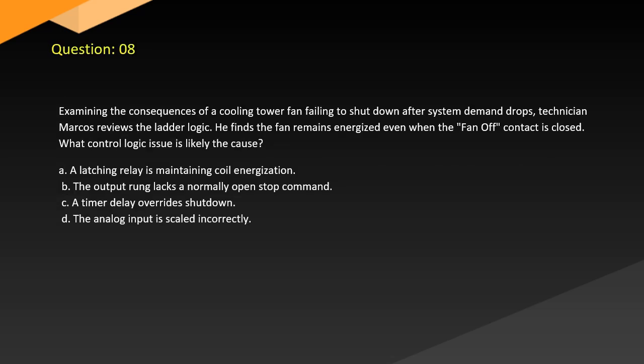Question 8. Examining the consequences of a cooling tower fan failing to shut down after system demand drops, technician Marcos reviews the ladder logic. He finds the fan remains energized even when the fan off contact is closed. What control logic issue is likely the cause? A. A latching relay is maintaining coil energization. B. The output rung lacks a normally open stop command. C. A timer delay overrides shutdown. D. The analog input is scaled incorrectly.